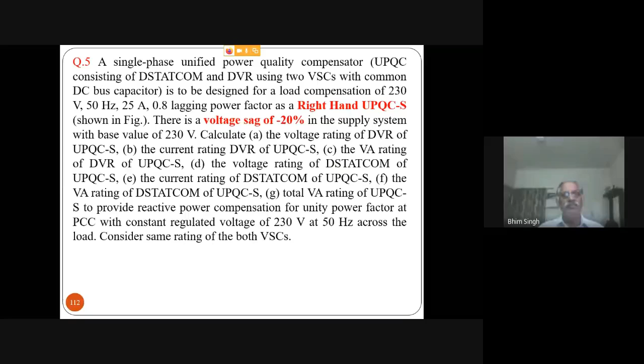Then, one of my recent PhD students extended the UPQC for solar generation. So what we do here is, you have a single phase UPQC, but we are putting solar with a boost converter on the DC link of it. So whether this power will go through the shunt back into the system and be consumed by the load, or it is put partly through the series also. When it is partly through the series, when the voltage is going down, you have to boost the voltage, so it will be injected here. But sometimes you have to take power here when there is a voltage swell, power should come there and then go back. This way, it is either consumed or goes to the load.